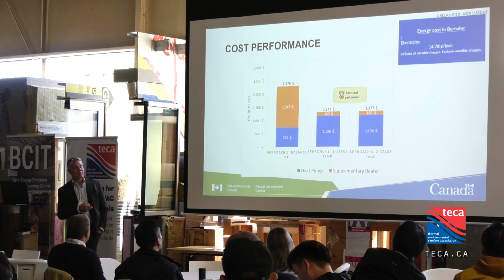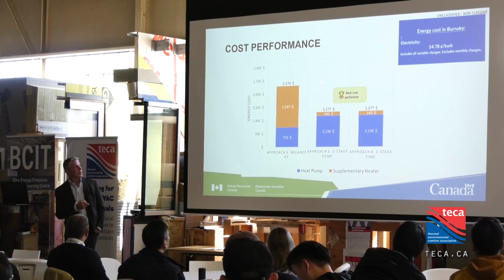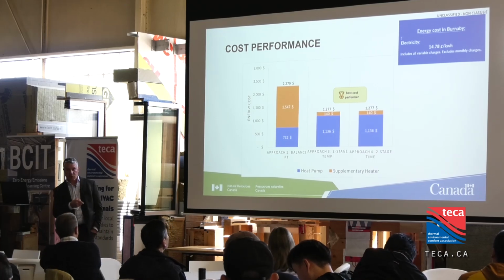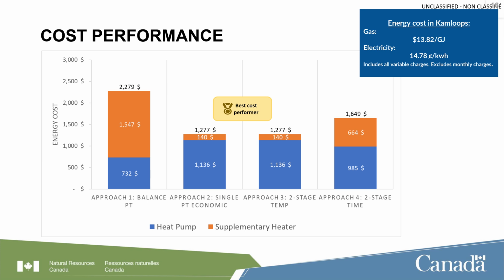Because as you can see here at 3 degrees Celsius, we're using quite a bit of that supplementary heat in this particular case for this 2.5-ton system. Okay, let's keep that in mind. This is going out with the full electricity cost as well, I guess, on the second tier, which Gary was mentioning earlier, as part of the study.